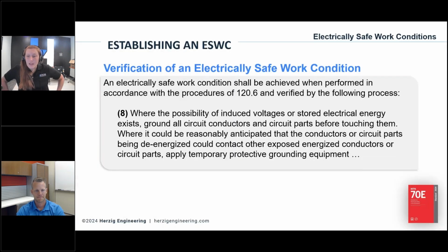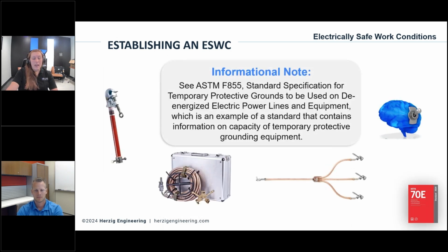All right, so we talked about step number 7. Now step number 8, which is the final step listed in the 70E. If there is a possibility for induced voltage or stored energy, backfeeds, things like that, you're going to ground out all the circuit parts before touching them. Or if there's a chance that you could have them re-energized, go ahead and ground them out as well. There are steps to making sure that they're placed in the right locations and that they have a high enough capacity to handle all the fault current and a low enough impedance to immediately cause operation of protective devices. All that information is in ASTM F855. More often than not, I see this in medium voltage applications as well. Not always, but that's more common.